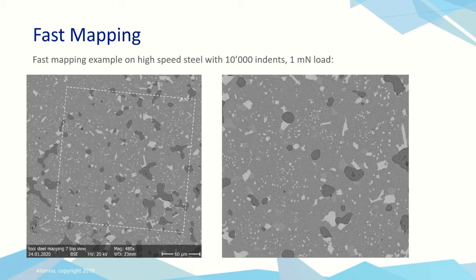One of the big advantages of the Alemnis system is it's displacement controlled, which means all the indents can be made to the same depth. Whereas if it was a load controlled machine, then if you hit a softer phase, your indents are going to be much deeper for the same load. So it's usually better to use displacement control for doing large maps.